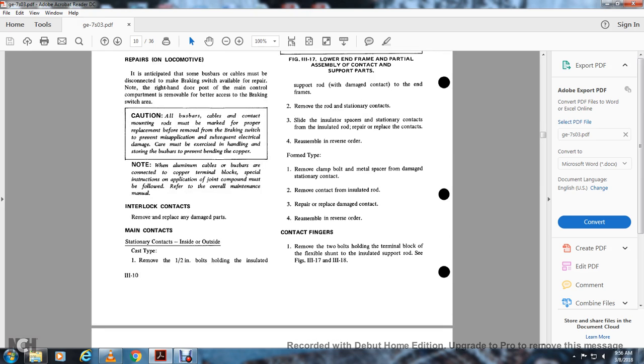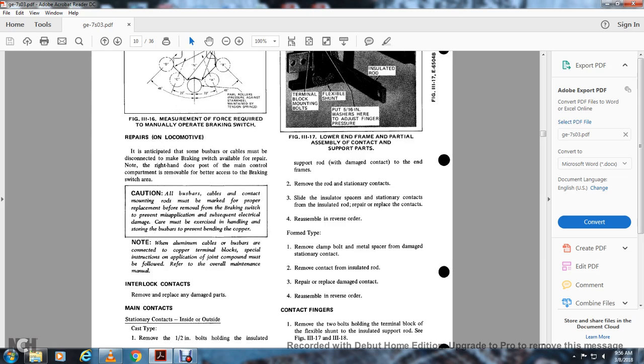Interlocking contacts: remove and replace any damaged parts. Main contacts: stationary contacts inside and out, cast type. Remove the 1/2 inch bolt holding the insulated support rod with the damaged contacts at the end of the frame. Remove the rod. Stationary contacts: slide the insulator spacers of the stationary contacts from the insulated rod. Repair or replace the contacts.